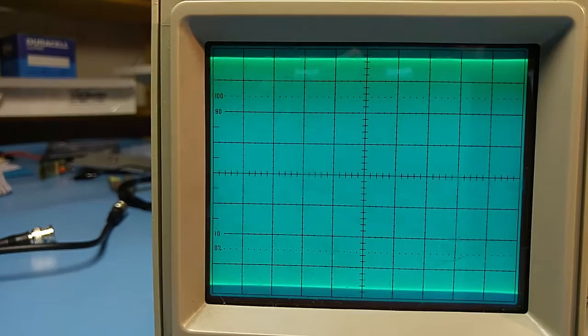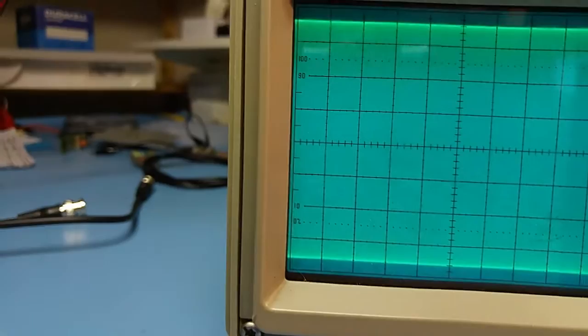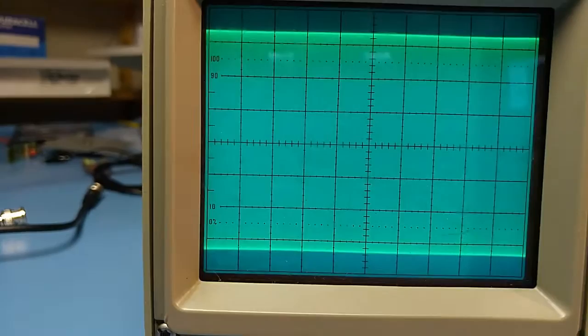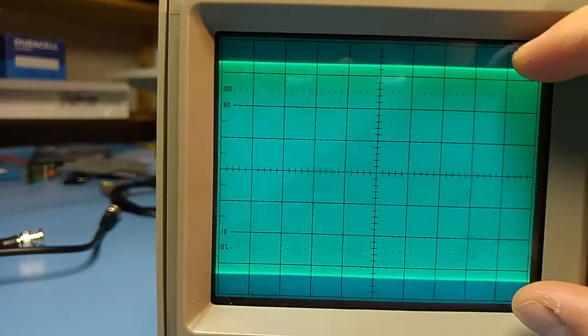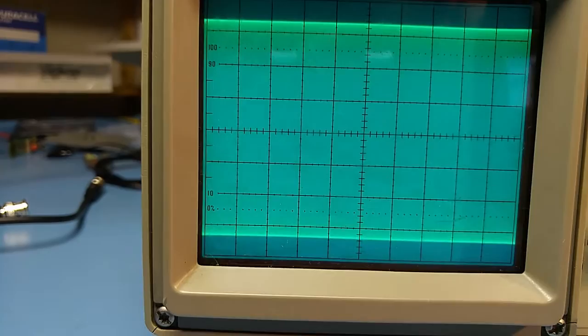10, 11, 12, 13, 14, 15, 16, 17, 18, 19, 20 megahertz. So, we know that the scope can at least achieve 20 megahertz bandwidth, which is the bandwidth of the scope. And then we continue 1, 2, 3, 4, 25 megahertz. And unfortunately, that's the limit of my signal generator. But we're still well within our normal bandwidth. So, we haven't reached the minus 3 dB. Therefore, the bandwidth is okay.